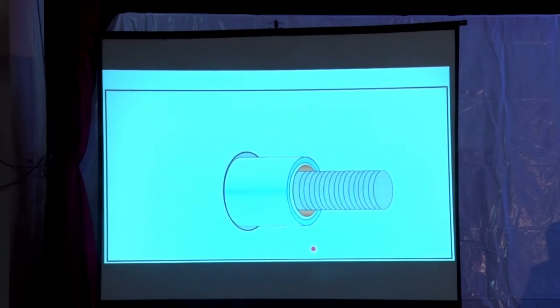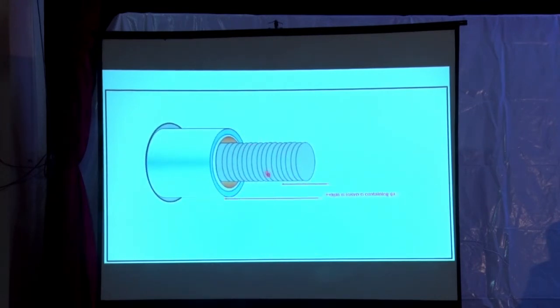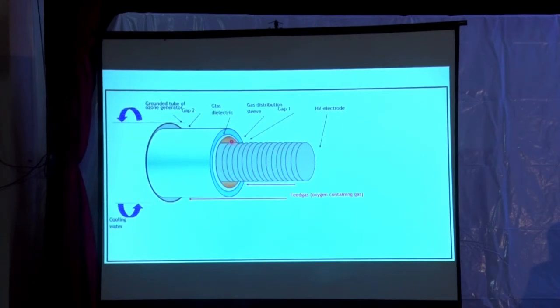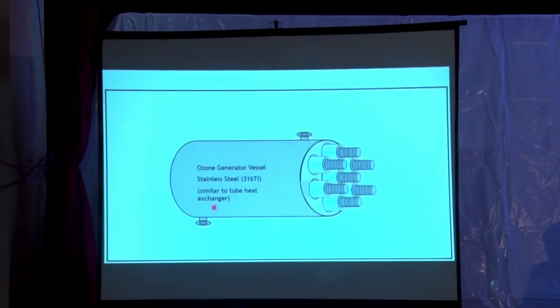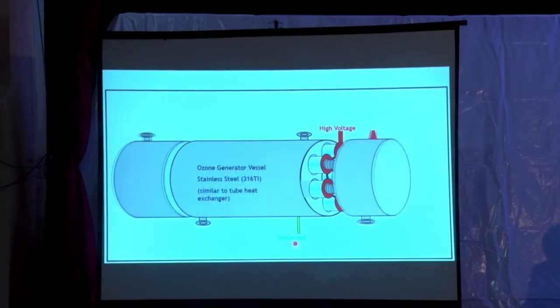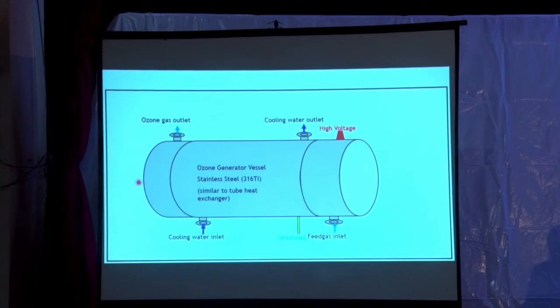At the macro level, this is the electrode, this is the gap, and this is the distribution sleeve that allows the oxygen into the electrode, and there is a slight gap, and over that we have a dielectric. Between the dielectric and the tube there is a gap again. Whatever oxygen we give at the inlet, partially it goes into the electrode and the remainder goes through as such, because we need only 10 to 10.5% concentration. All these electrodes are connected to a high voltage power supply, which is grounded. Both sides are closed with a dome.